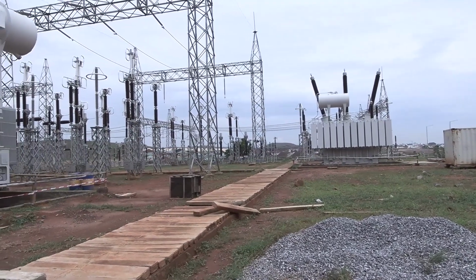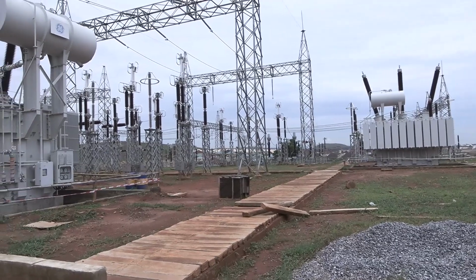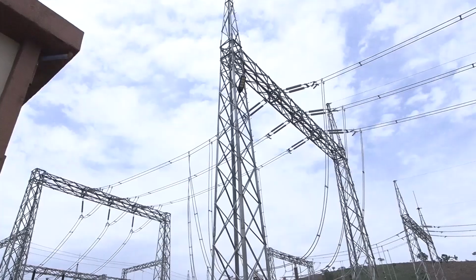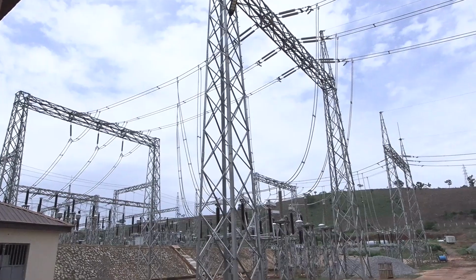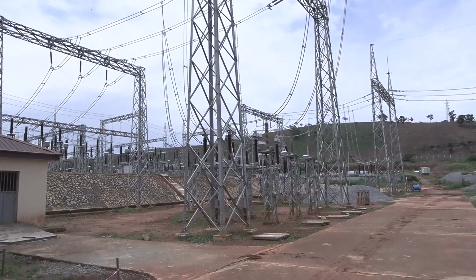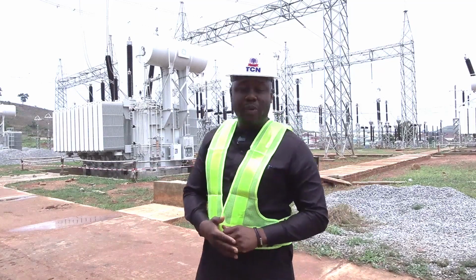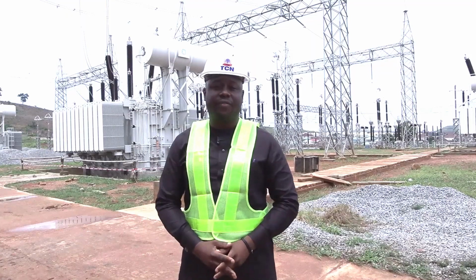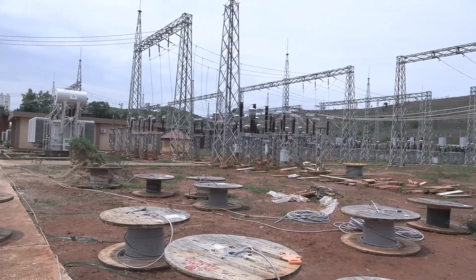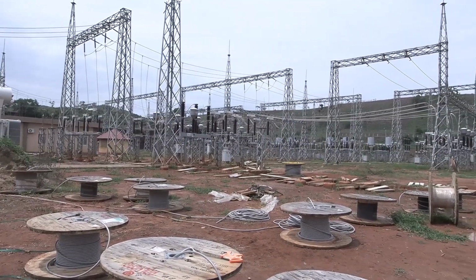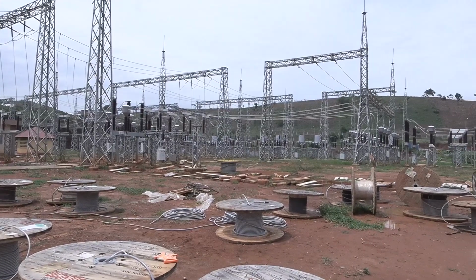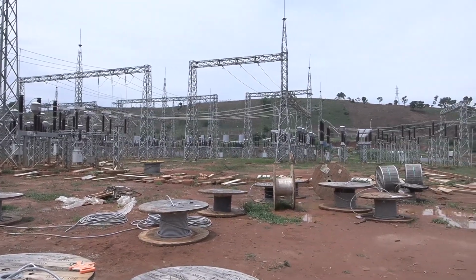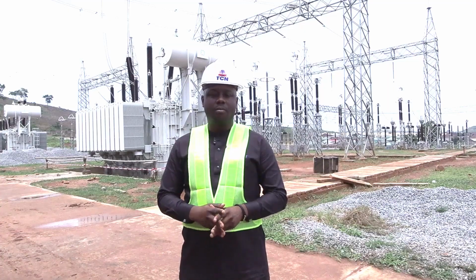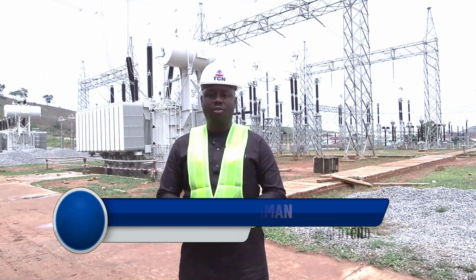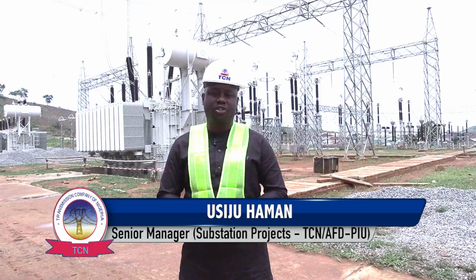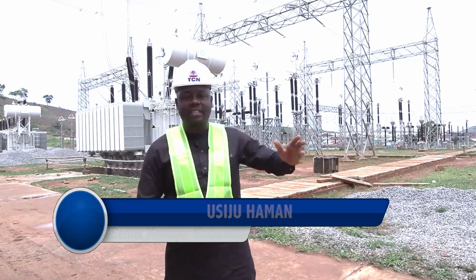This station would increase the transmission capacity by 240 megawatts, and we have 9 33 kV feeders to evacuate to the Apo and its environs. This station would be radiating 33 kV feeders by the Abuja Electricity Distribution Company. But most importantly, this station would also be feeding through the Abuja Electricity Distribution Company, the African Medical Center of Excellence.